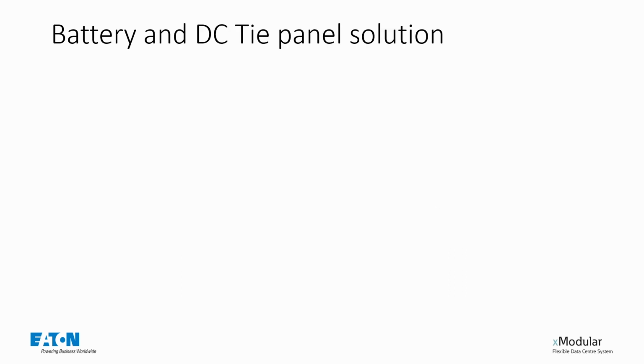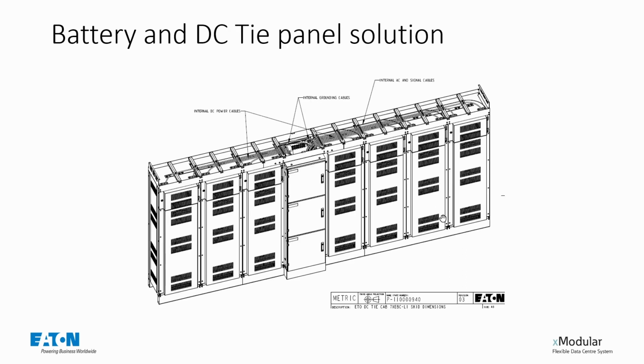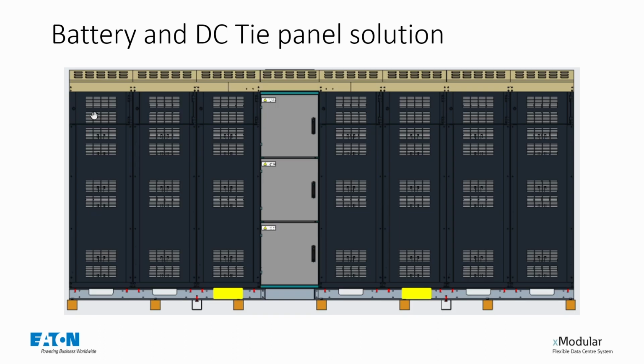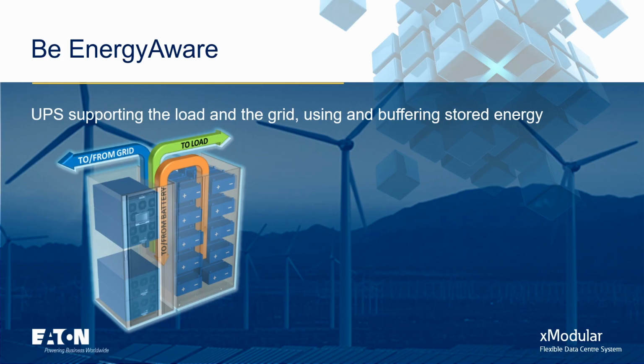What does this look like? So inside, there'd be a bunch of lithium racks, and that's a typical picture of what an industry professional could provide, where you've got lithium batteries and a battery distribution system that you would just simply connect to your module. It's safe. It's separate, and that's what matters. In a data center, you want to reduce a single point of failure, and of course, if you have an incident with a battery, that can be a single point of failure. Therefore, we promote, and others promote, the fact that the battery is separate from the energy center.